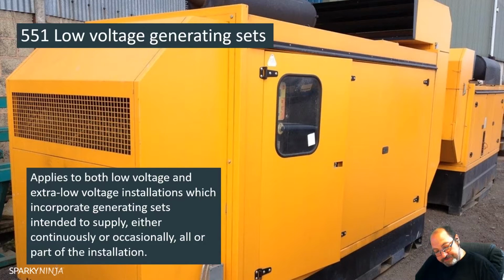Okay, also shall not be exceeded. So, I mean, we've covered this a few times now. The protection against overcurrent. The devices must be selected to tolerate the prospective fault currents that can occur. Now, obviously, when we have generation sources, we may have a varying fault current depending on the earthing effect and the sources of generation.